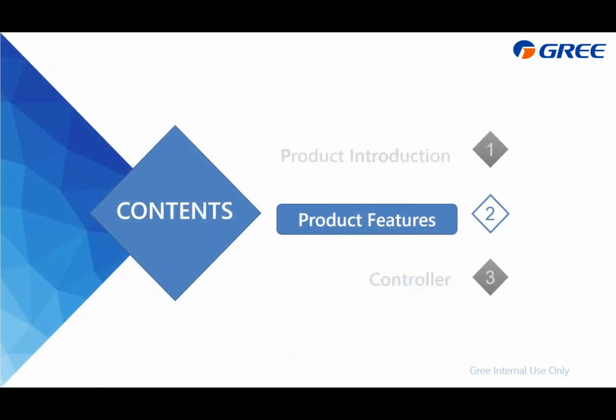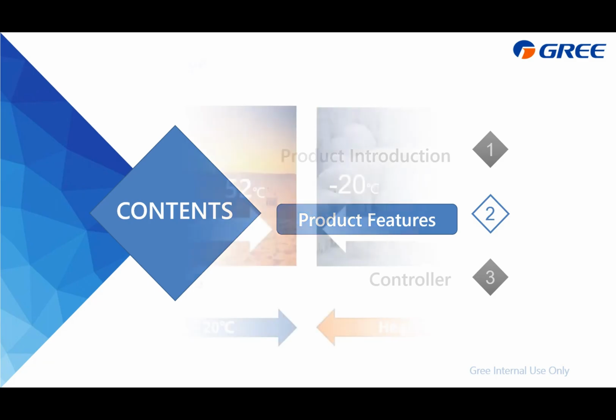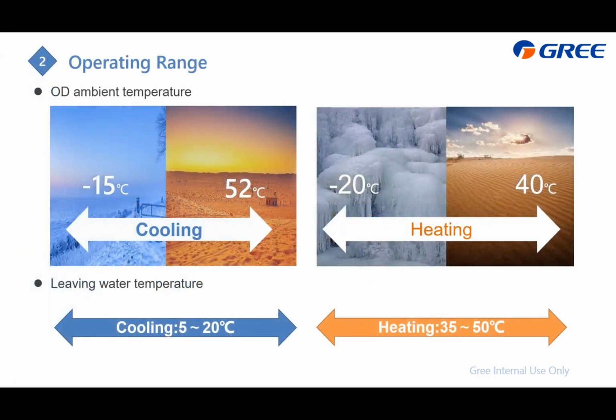The second chapter is product features. This is the operating range. For cooling, the outdoor ambient temperature is -15 to 52 degrees, and within this range we can offer you chilled water from 5 to 20. And for heating, the outdoor ambient temperature is from -20 to 40 degrees, and within this range we can offer you hot water from 35 to 50 degrees.